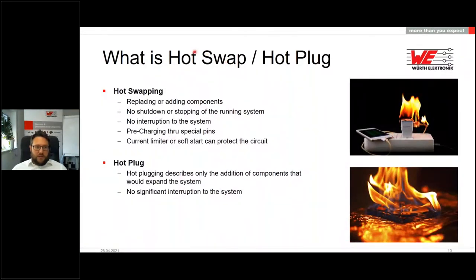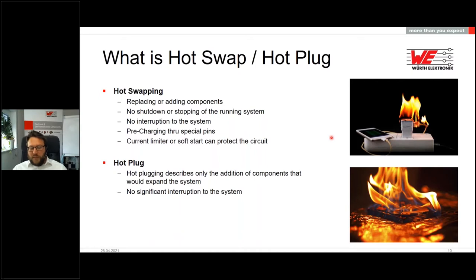A few words about hot-swap and hot-plug — these terms are often used similarly. Hot-swap is the replacing or adding of components while the system keeps running, without shutdown. This is achieved via pre-charging through special pins, current limits, or soft-start peripherals. Hot-plugging more or less only describes the addition of components that expand the system without significant interruption to it.